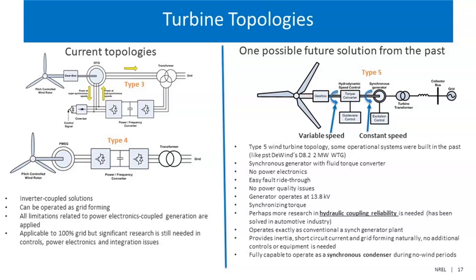This technology has been demonstrated in the past. In fact, NREL tested one of the first 2-megawatt units at our site. That was a drivetrain from a DeWind. But that's basically a synchronous generator-based wind turbine with a hydraulic torque converter. So it operates basically as any conventional plant. It can also provide synchronous condenser-like services at times when there is no wind. So I'm not saying this is a solution, but this is something maybe worth considering, essentially going back in time and seeing if this now old technology makes sense. In fact, a few of these turbines have also been deployed in Sweetwater in Texas.